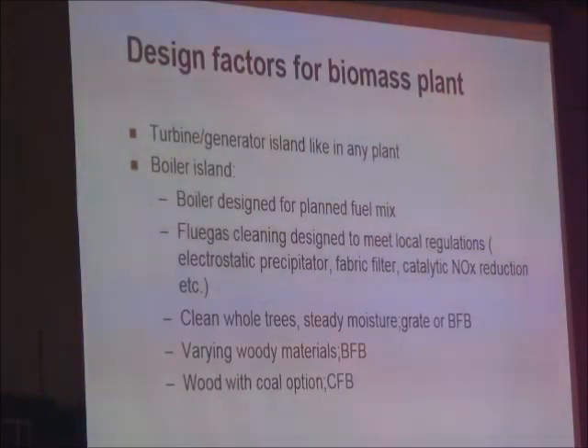For boiler options: if the fuel supply will be clean whole trees or clean wood residues, a grate boiler works fine, or a bubbling fluid bed. If it's all kinds of logging residues with very varying material and moisture, a bubbling fluid bed is a good choice. And if there's a coal option, or sometimes a big share of very dry material coming into the boiler, then a circulating fluid bed technology is picked for the boiler.